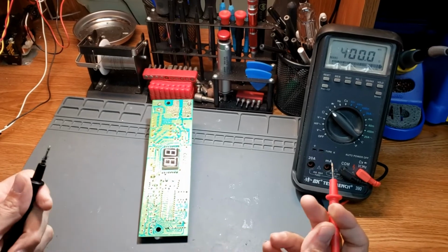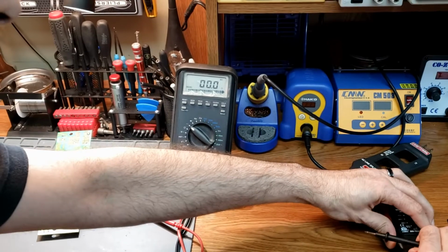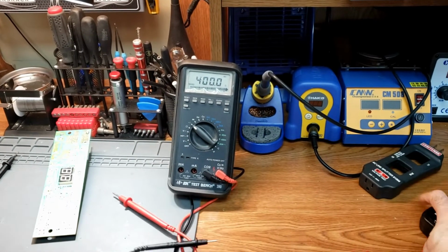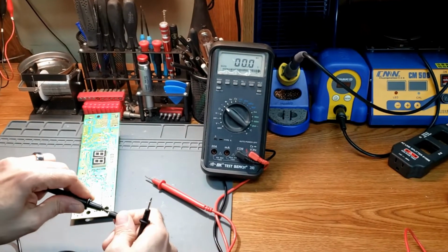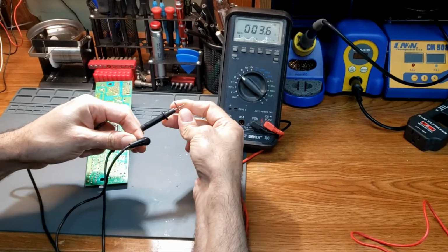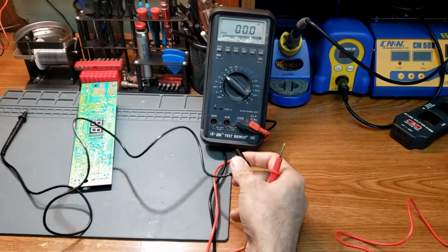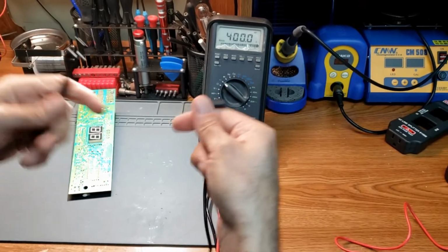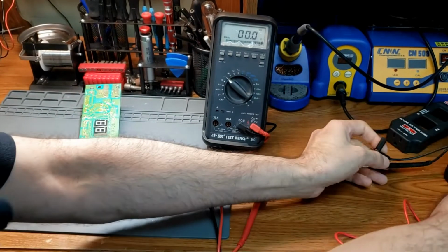Sometimes you check it from the end of one wire to another, like if you don't know if there might be a break in the wire. Say, for example, you need to make sure that the voltage can go through from one place to the next. So if we touch the metal part on the inside of that terminal there, and then touch this one here, see, we have the continuity right there. If for some reason you check two different ends of the same wire and there was not electrical continuity, that would tell you that the wire itself is bad.